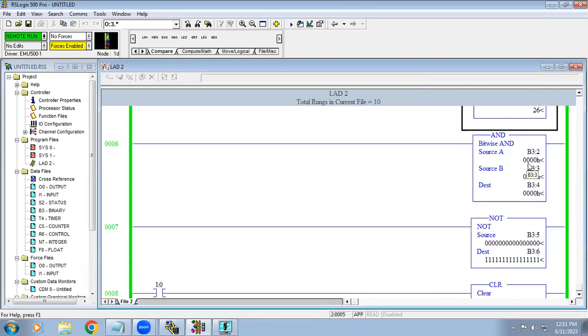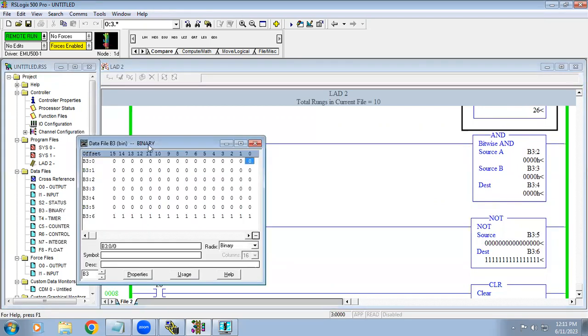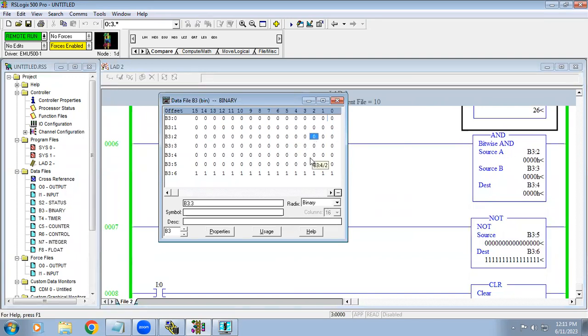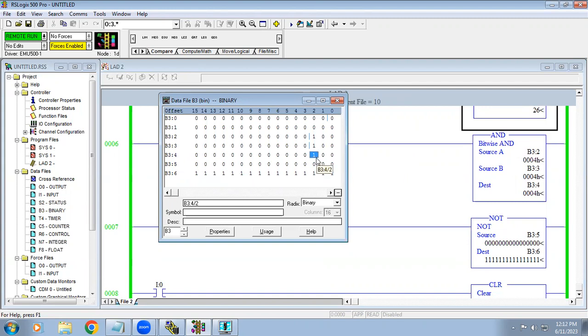The bitwise AND function works on binary values bit by bit — when both A and B bits are one, the destination bit is one. You can also use the result address bits directly as inputs in your program. For example, B3 colon 4 slash 2 — that specific bit — can be used as an input to activate a process. This means all 16 bits can be used as inputs, so in a single bitwise AND function you can execute 16 logic operations.